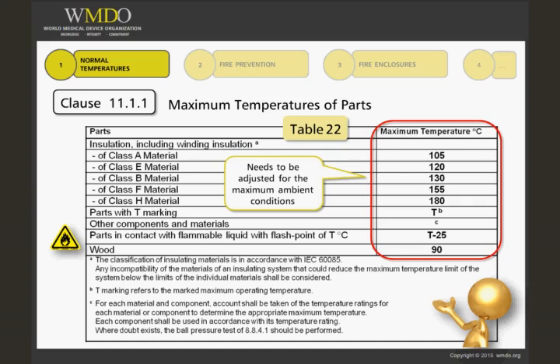Remember, all of these limits are for temperatures measured on internal components with the equipment running at the maximum ambient temperature or adjusted for the maximum ambient temperature.